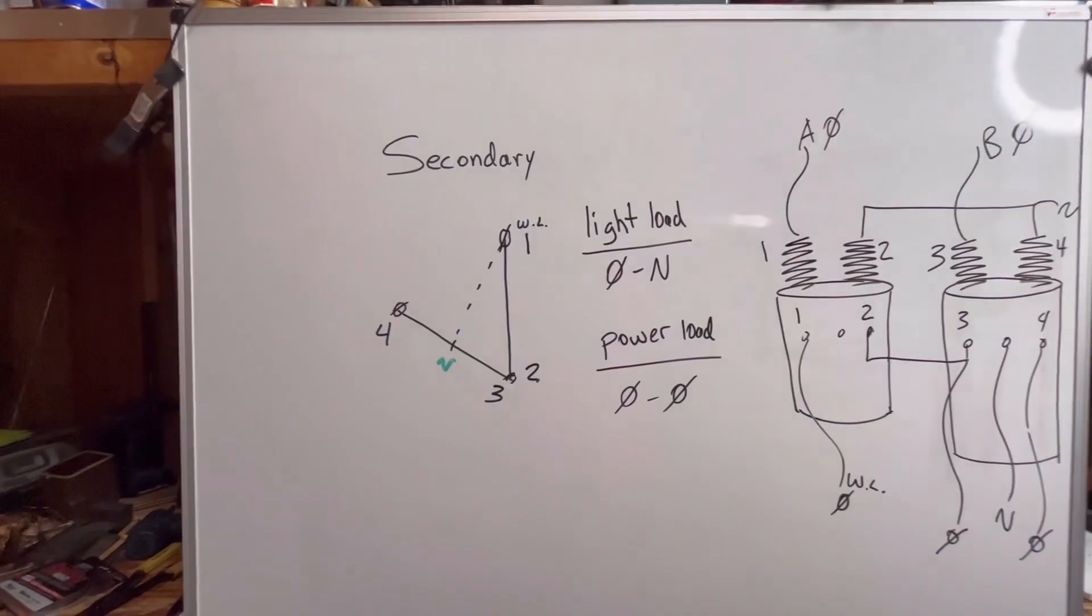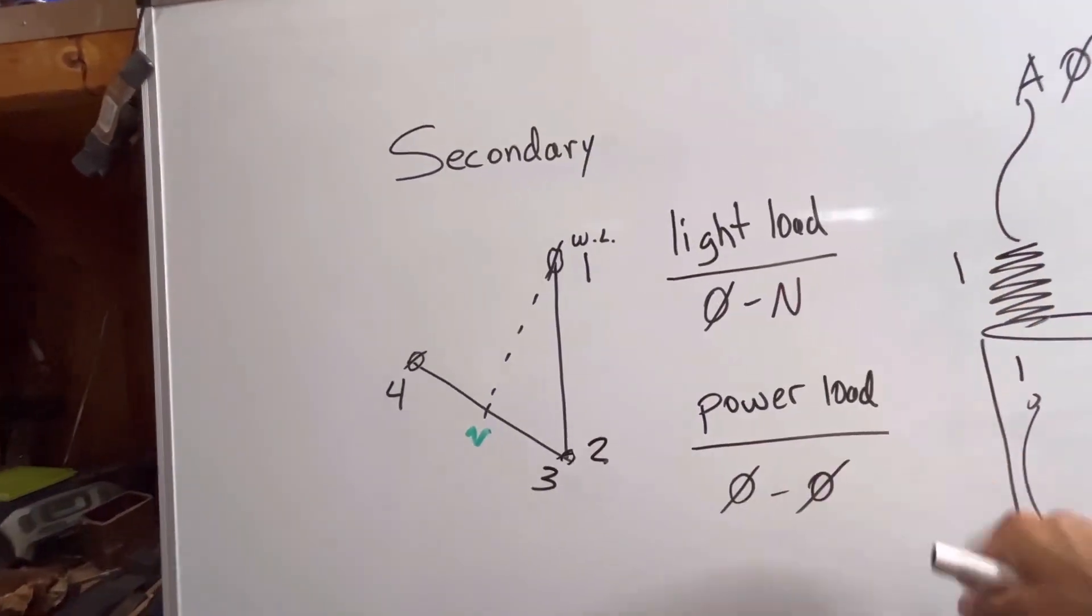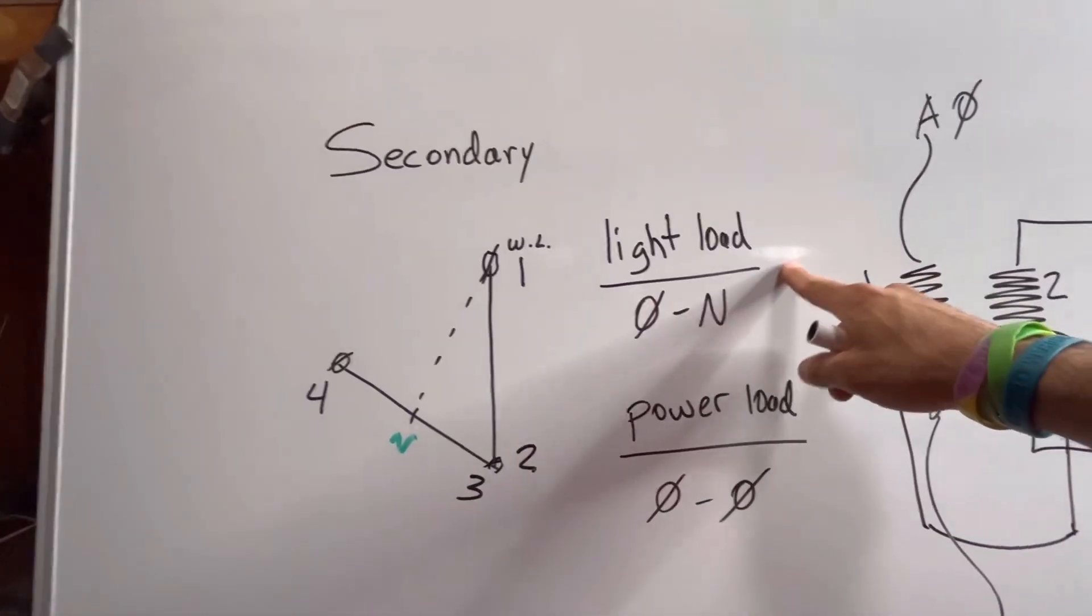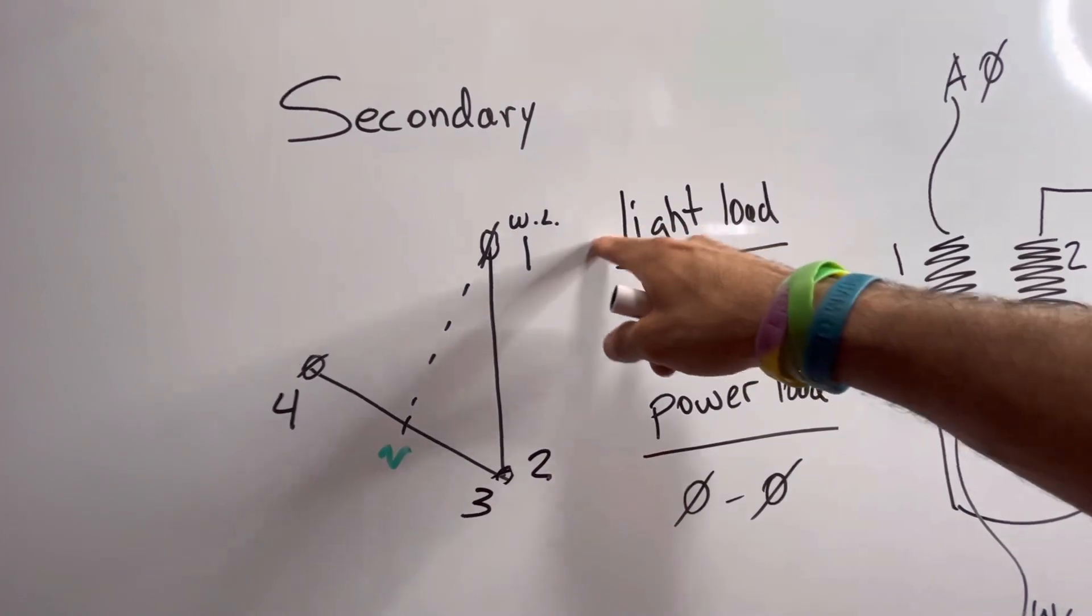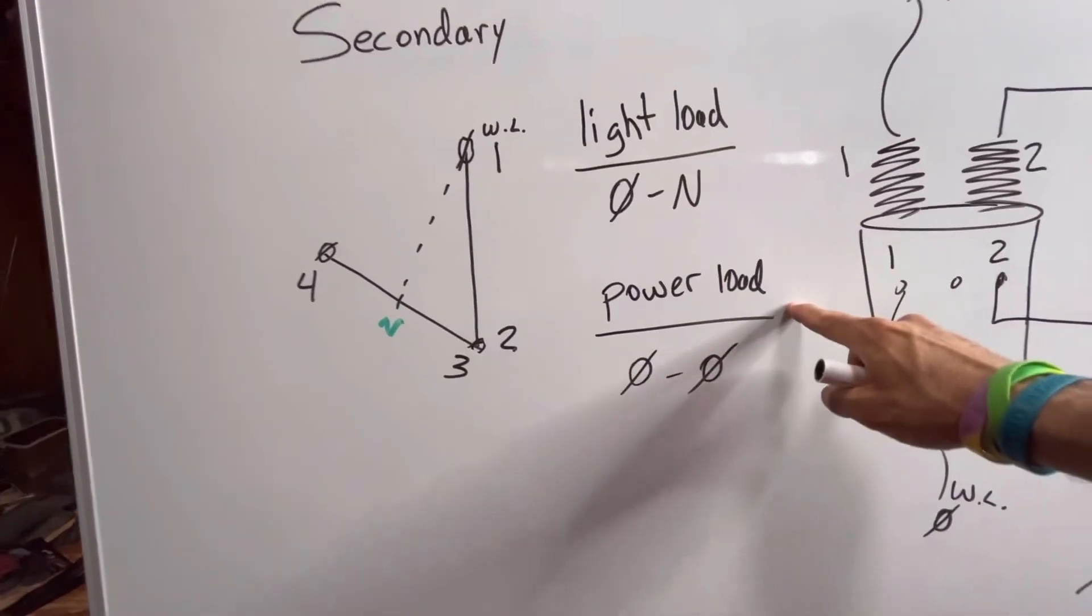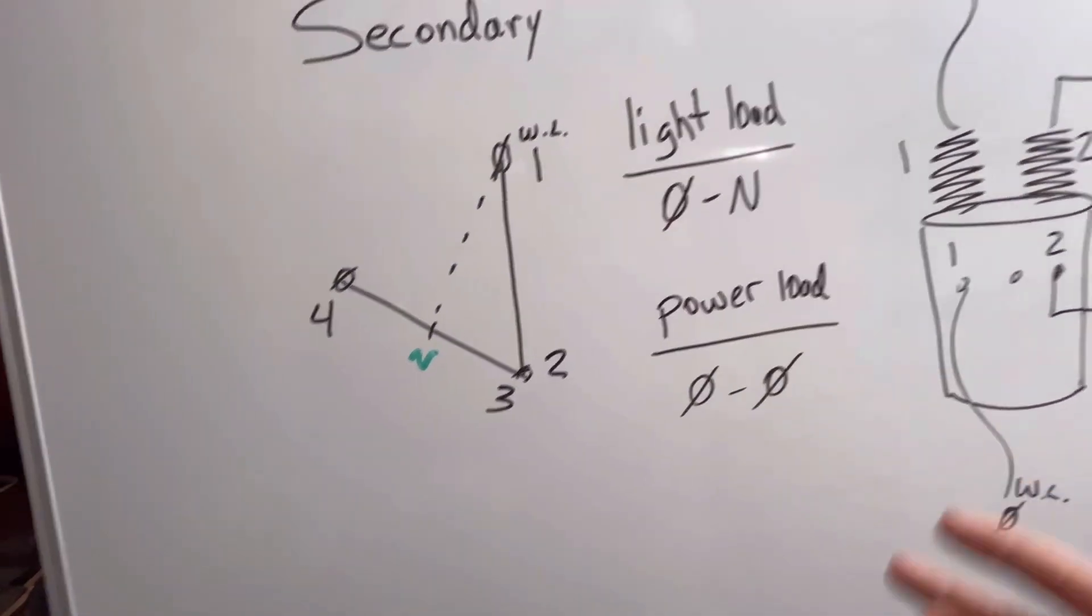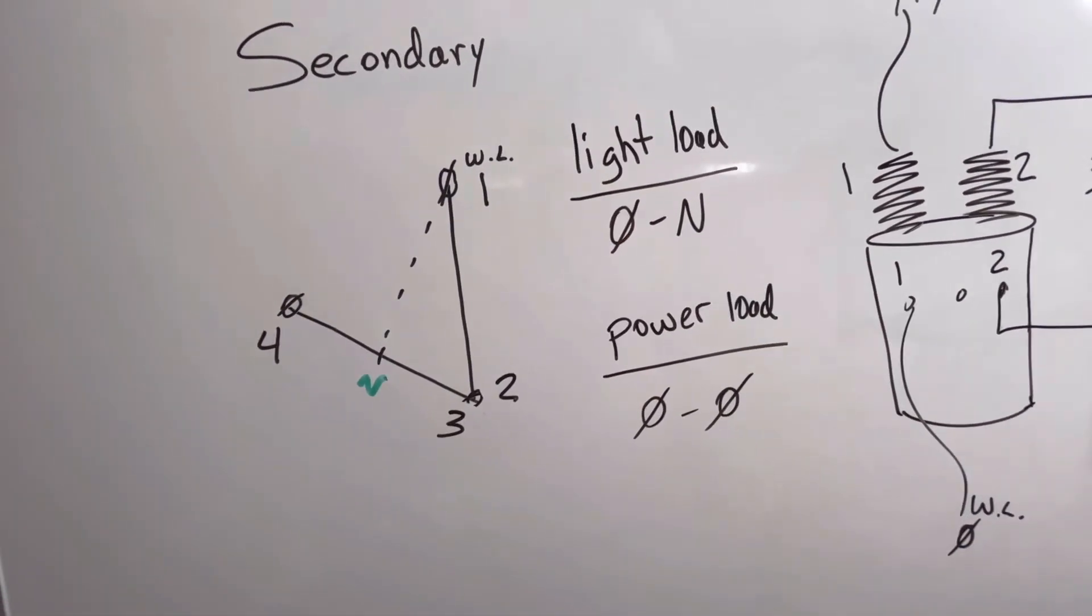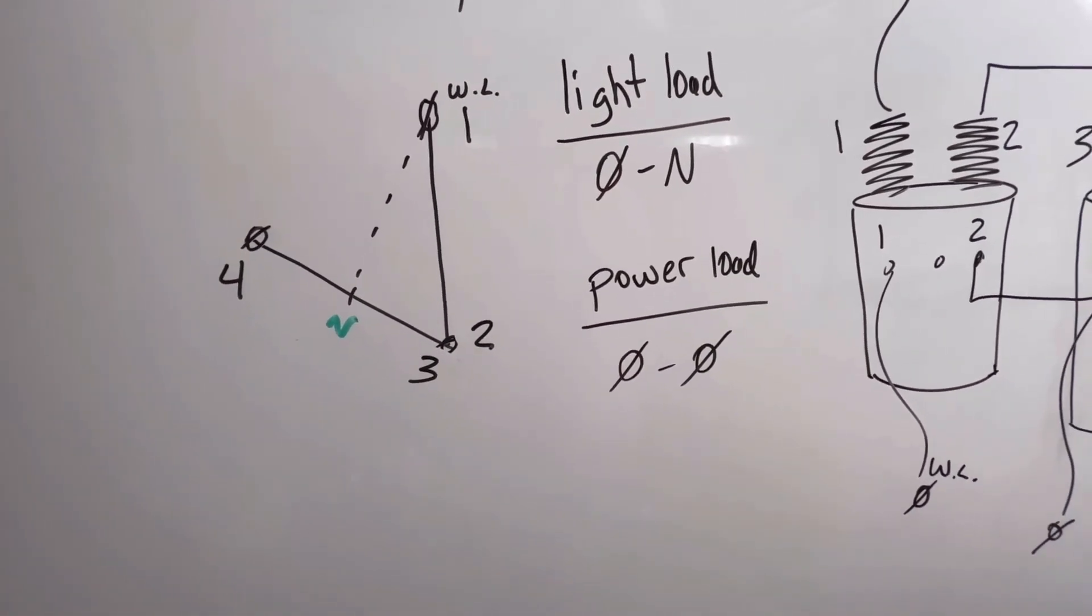So the terms light and power are just references to what type of load our customer has. The lighting load was called the lighting load because it was typically the potential that ran all the lights in the building, or the phase-to-neutral load. The power load is a reference to the phase-to-phase load. So your three-phase motors, your 240 appliances, all that kind of stuff, air conditioners, everything. That's your power load.